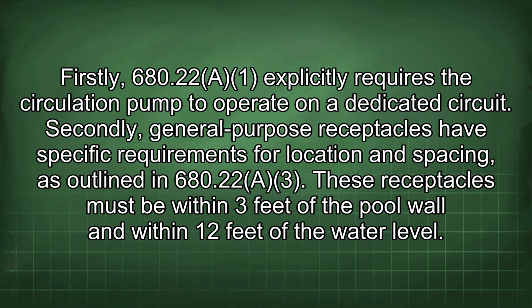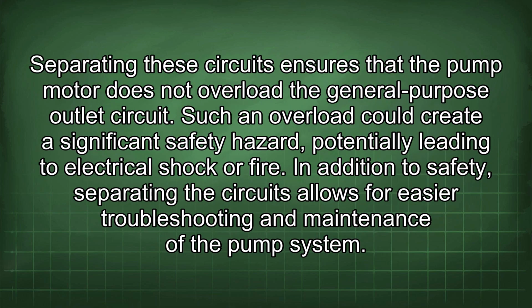Secondly, general-purpose receptacles have specific requirements for location and spacing, as outlined in 680.22a3. These receptacles must be within 3 feet of the pool wall and within 12 feet of the water level. Separating these circuits ensures that the pump motor does not overload the general-purpose outlet circuit. Such an overload could create a significant safety hazard, potentially leading to electrical shock or fire. In addition to safety, separating the circuits allows for easier troubleshooting and maintenance of the pump system.